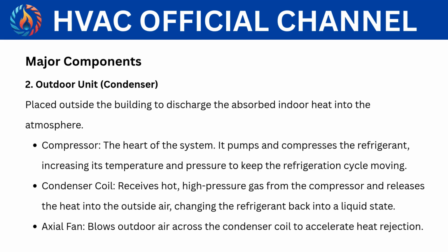2. Outdoor unit, condenser. Placed outside the building to discharge the absorbed indoor heat into the atmosphere. Compressor, the heart of the system. It pumps and compresses the refrigerant, increasing its temperature and pressure to keep the refrigeration cycle moving. Condenser coil. Receives hot, high-pressure gas from the compressor and releases the heat into the outside air, changing the refrigerant back into a liquid state. Axial fan. Blows outdoor air across the condenser coil to accelerate heat rejection.